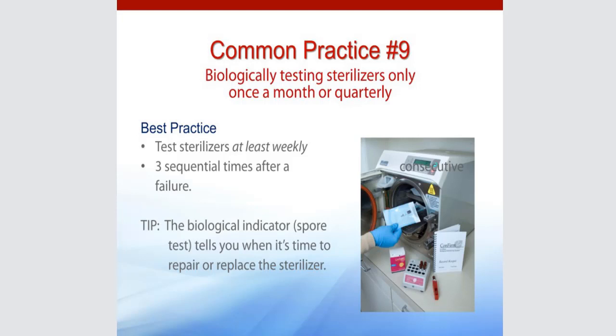So it means that you put in one spore strip and you run the cycle. You put in another spore strip and you run another cycle. You put in the third spore strip and you run another cycle. You can't put 3 spore strips into one cycle and run it. And remember, when you're working with tabletop sterilizer, best practice is you run it with a full load. Your BIs should not be run on an empty load with the tabletop sterilizer. That's very different from some of the larger wall sterilizers that are in fact run empty.